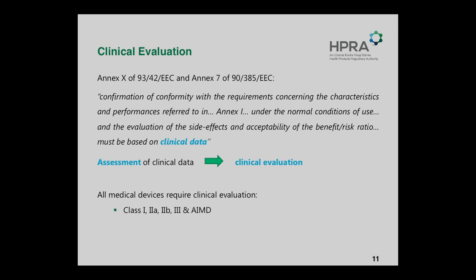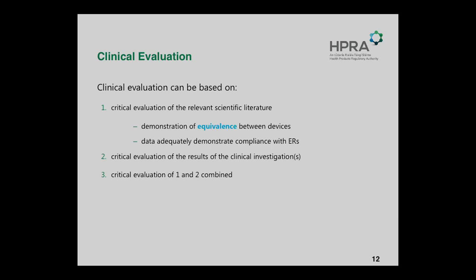The definition of clinical investigation is fairly similar in part to a clinical study — it's just what we call it under the legislation. The annexes in the directives relate to clinical investigations. One very important standard in this area is ISO 14155, which deals with good clinical practice for medical devices. That's really where the role of the investigator, the sponsor, and all the relevant elements are outlined, and it's a worthwhile document to have.